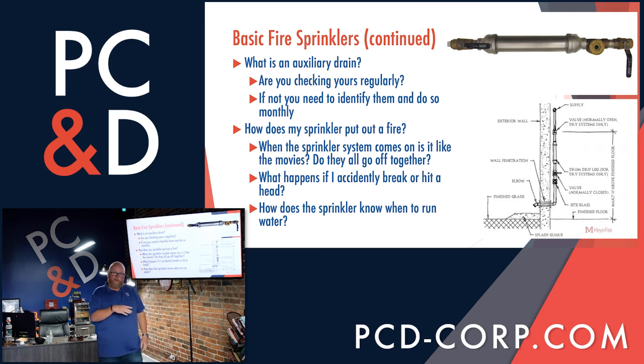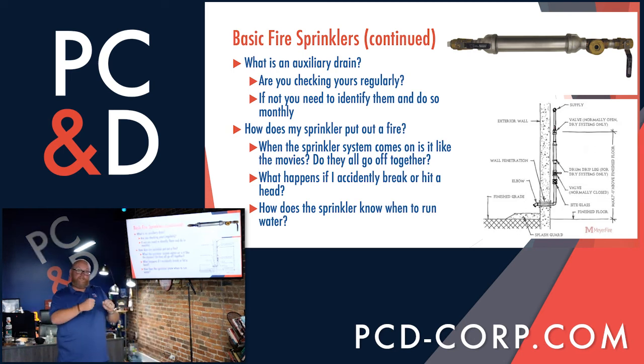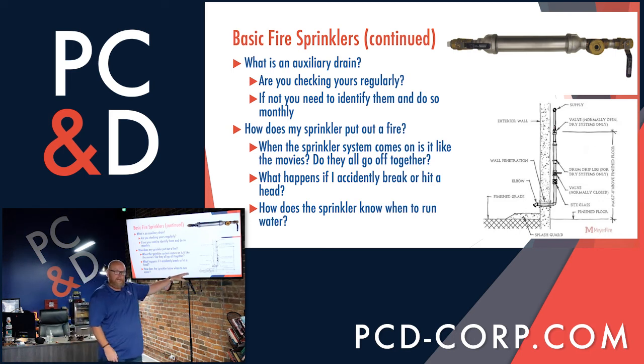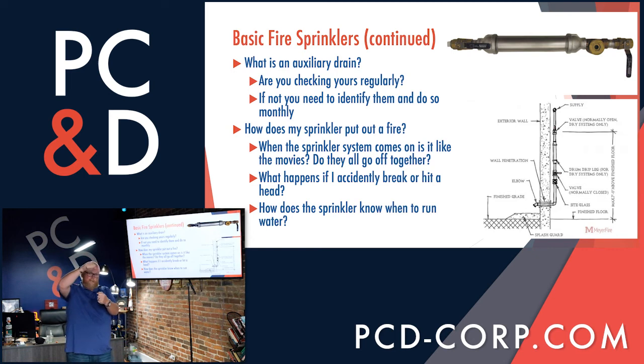You get rid of the water. You're going to do that a series of times until you no longer see or hear water coming out of the system. Depending on how frequently you do that, I would recommend at least monthly in the winter months. In the summer, you might get by every other month, but it depends on what your policy is. You need to go identify all of your low point drains and drain them until you have no more water. Remember, top valve closed, bottom valve open.